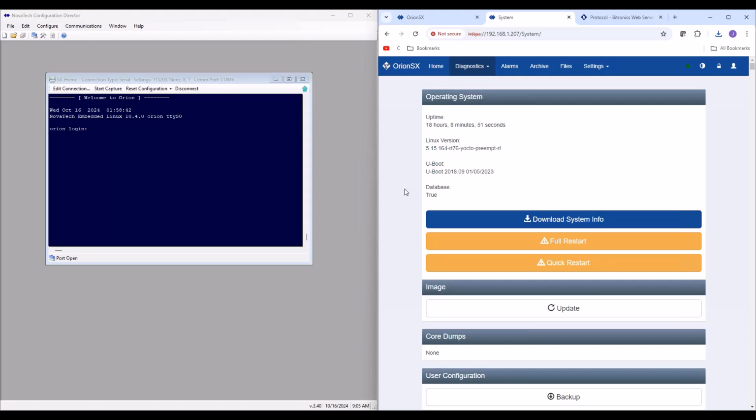Maybe troubleshooting with our tech support team hasn't fixed any issues. Sometimes a factory wipe can wipe out any secret bugs that are living in the Orion. And thirdly, if you ever downgrade your firmware, you'll try and log in, and you may notice that the Orion's not letting you log in. It's not recognizing your username and password. That's because when doing a firmware downgrade, you have to also do a factory wipe after the downgrade. So, a couple instances where a factory wipe might be necessary.